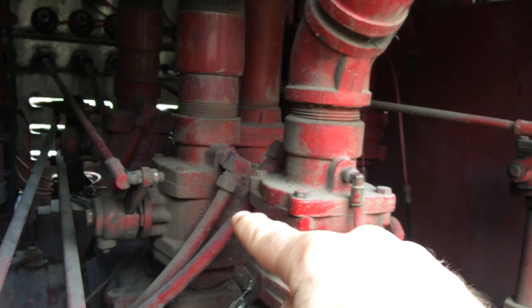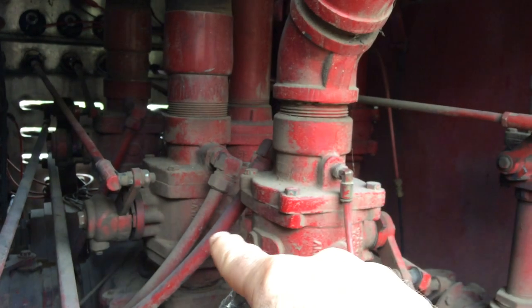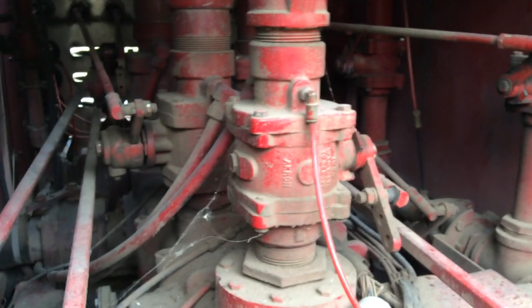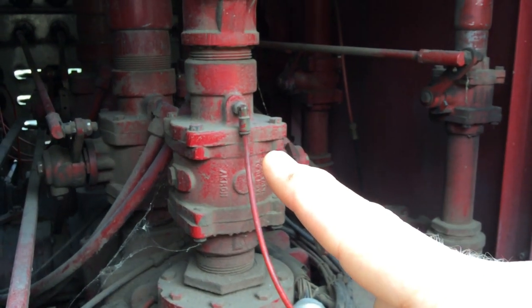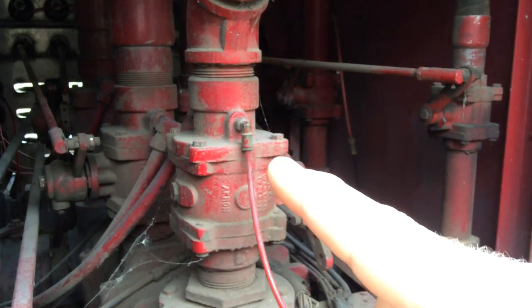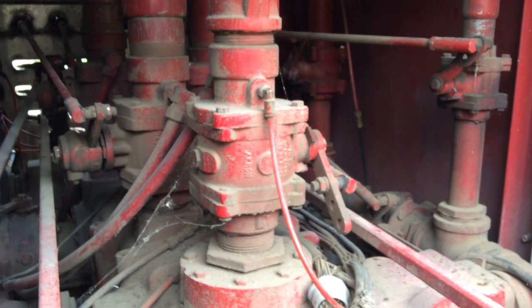On the back side of this are drains — that's your drain for that valve, and there's one right here that goes to this valve. Pretty commonly, on any of these control valves, you're going to have a gauge line. On a discharge control valve you can have a gauge line, you can have a drain, you can have a valve — and you should be able to identify those.